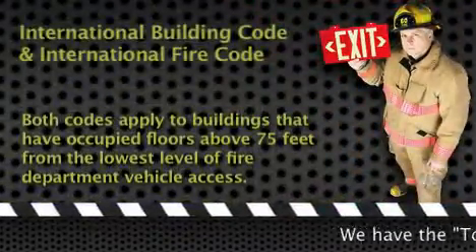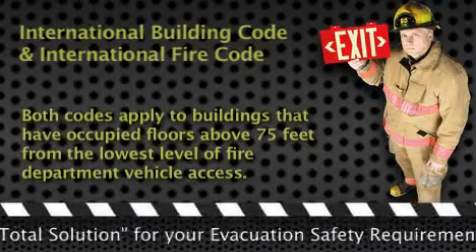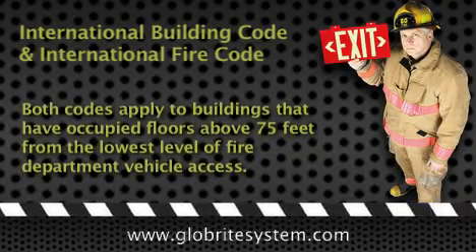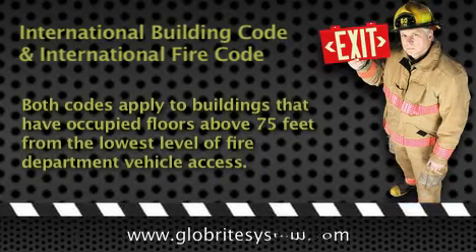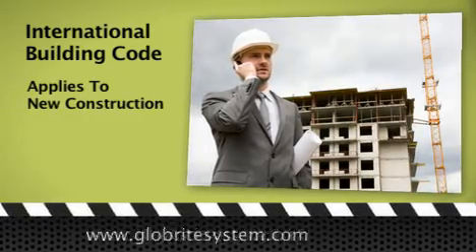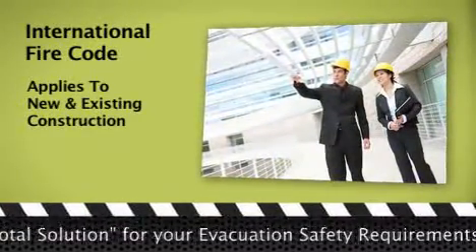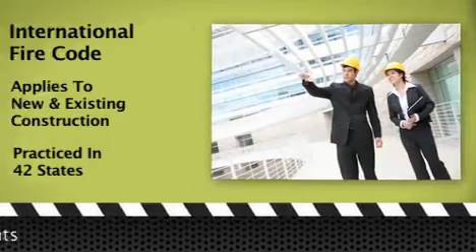The International Building Code and the International Fire Code apply to the institutional, educational, business, hotel, public safety, and R1 residential buildings that contain occupied floors above 75 feet from the lowest level of fire department vehicle access. The International Building Code governs new construction and is practiced in all 50 states. The International Fire Code governs new construction and existing construction and is practiced in 42 states.